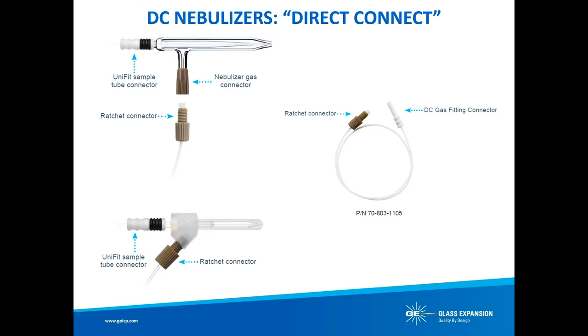Glass Expansion recently introduced the Direct Connection, or DC, gas line — an inert, metal-free, ICP-specific gas line upgrade for our U-Series nebulizer product line. The reliable ratchet click-and-seal fitting to the nebulizer gas arm ensures a leak-free gas connection by clicking or ratcheting when a proper seal has been achieved, preventing over-tightening. At the other end of the DC gas line is an ICP-specific quick-connect to the argon gas supply, helping to maintain optimal back pressure for consistent day-to-day nebulizer performance.